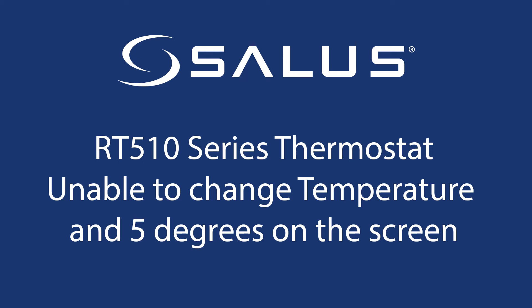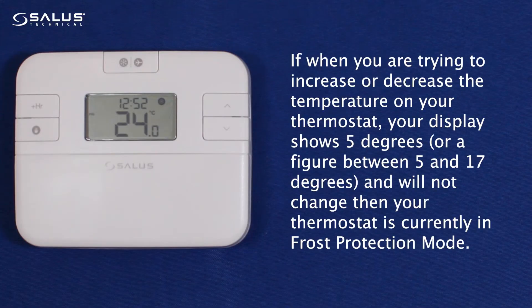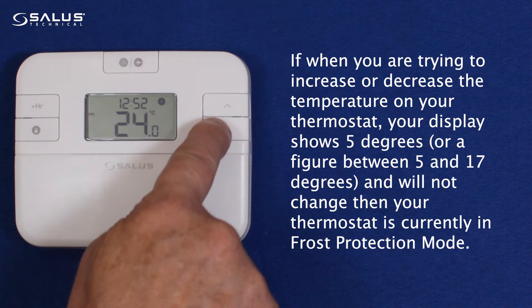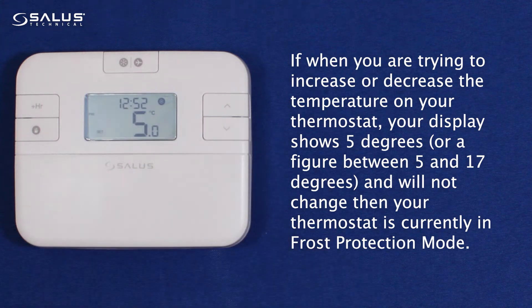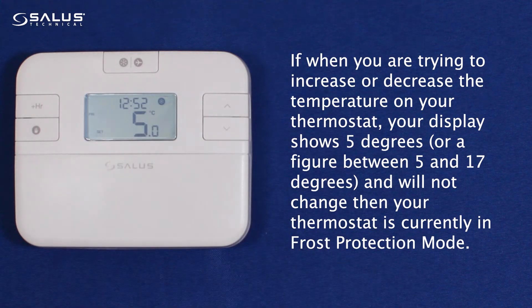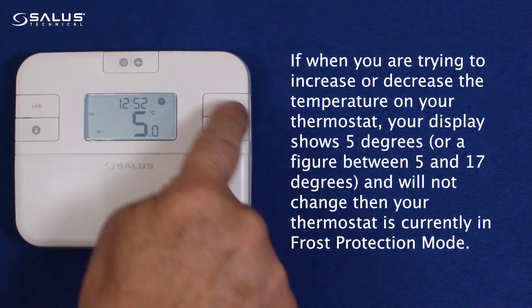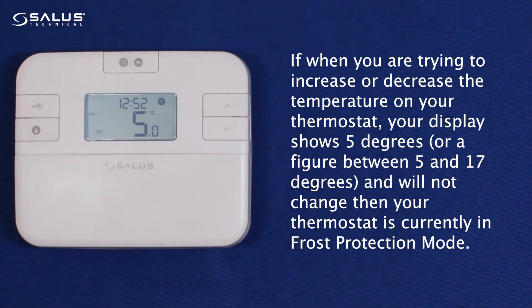RT510RF: unable to change temperature and 5C on the screen. If when you are trying to increase or decrease the temperature on your thermostat, your display shows 5 degrees, or a figure between 5 and 17 degrees, and will not change, then your thermostat is currently in frost protection mode.